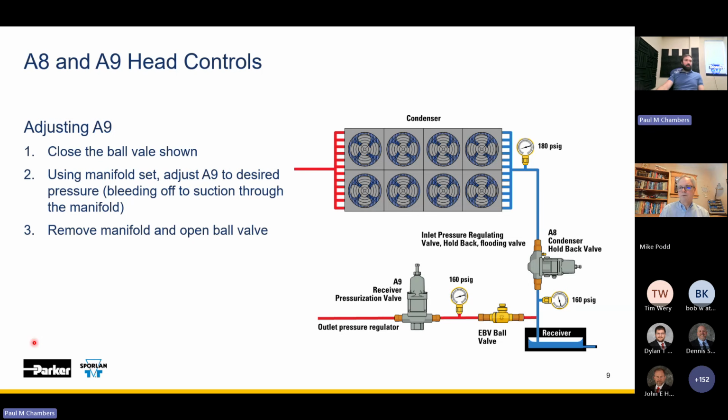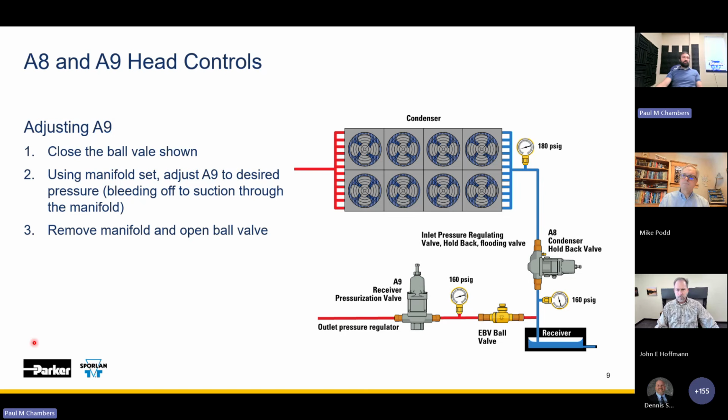We'll do one more, the last one, and then we can let everyone go. It says the ORD is a 20 psi differential valve, but will not start opening till 16 psi of differential, and will close again once pressurizing the receiver to 16 from discharge?